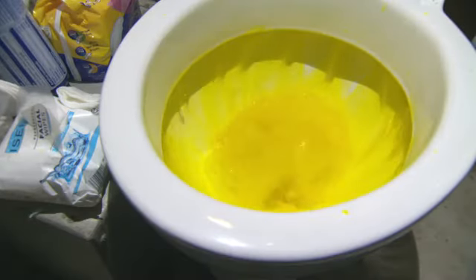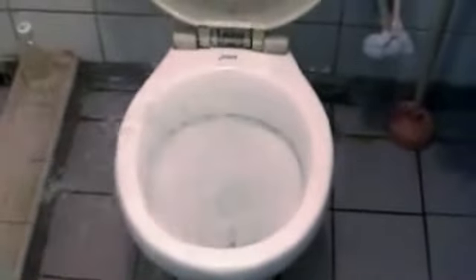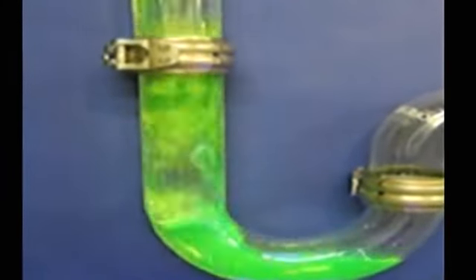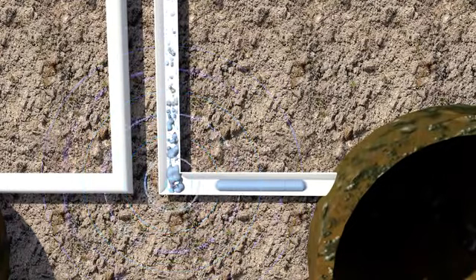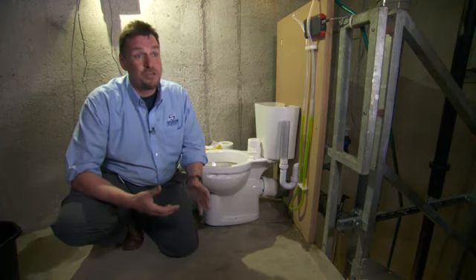What we're finding now is that a lot of the venting is undersized, and that leads to problems with exploding toilets. If you stay in hotels, often you can hear the floor drains and hear this banging. When air pushing down is blocked by too much waste in the pipe, it has nowhere to go but up. If you hit the base of the stack and you have a water curtain, the positive pressure reflects back up the drainage system at 320 meters a second — the speed of sound. So it's an acoustic event.